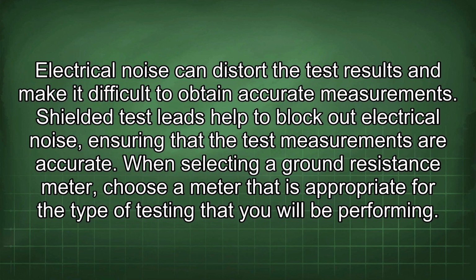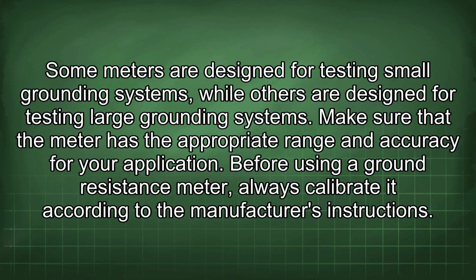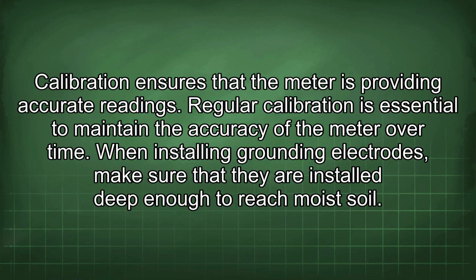When selecting a ground resistance meter, choose a meter that is appropriate for the type of testing that you will be performing. Some meters are designed for testing small grounding systems, while others are designed for testing large grounding systems. Make sure that the meter has the appropriate range and accuracy for your application. Before using a ground resistance meter, always calibrate it according to the manufacturer's instructions. Calibration ensures that the meter is providing accurate readings.